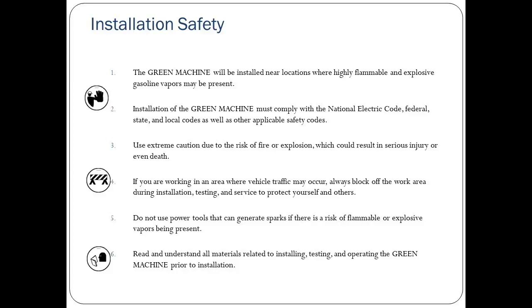Starting with safety, remember that a GDF is a Class 1, Division 2 hazardous location. The Green Machine will be installed near locations where highly flammable and explosive gasoline vapors may be present. Installation of the Green Machine must comply with the National Electric Code, federal, state, and local codes, as well as other applicable safety codes.